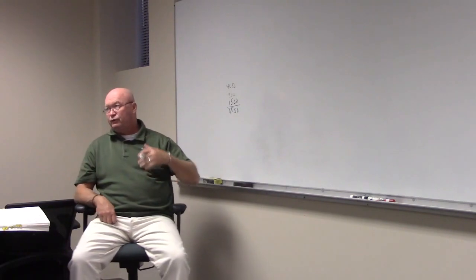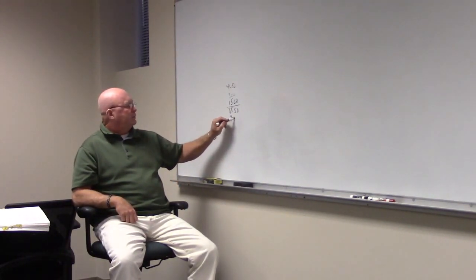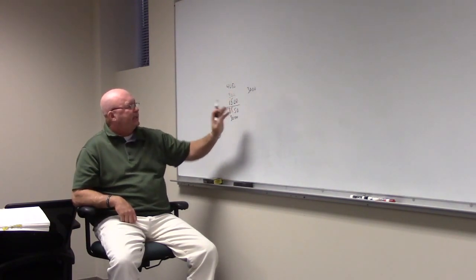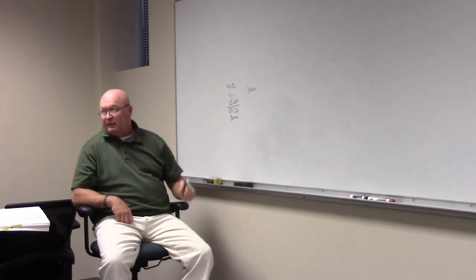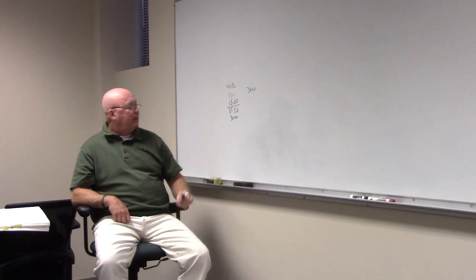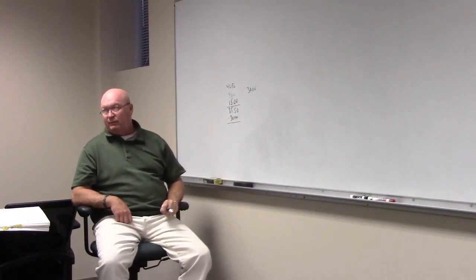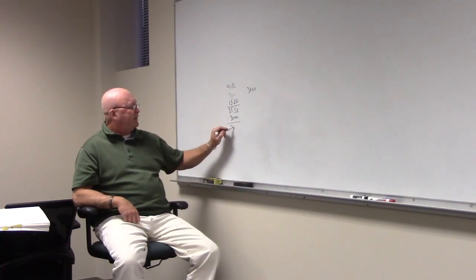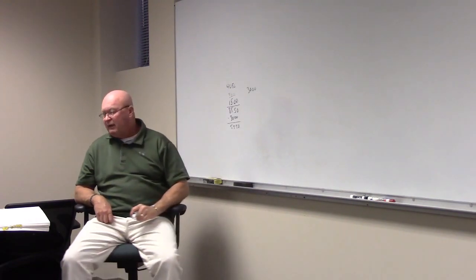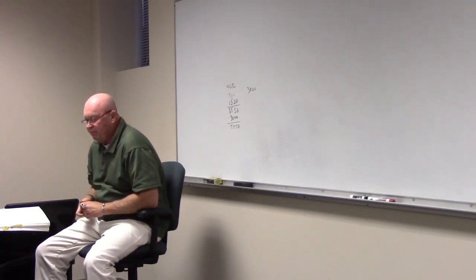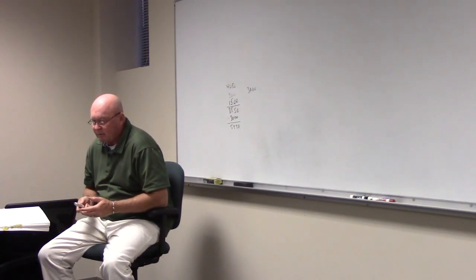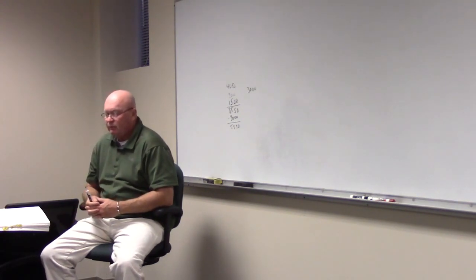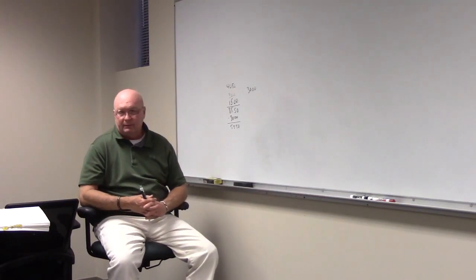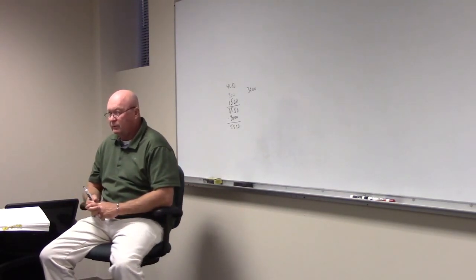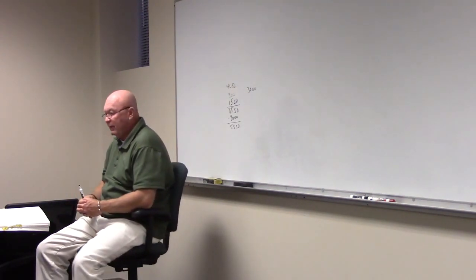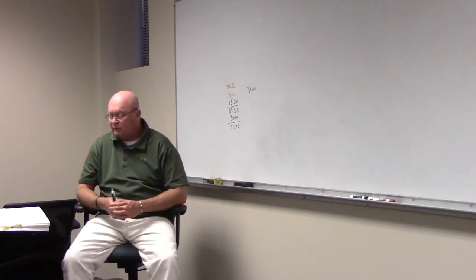All right, it says the first 3,000 is 100%. So I'm going to take that 3,000, I'm fixing to take it out, but I have to count it at 100%. So I'm going to plug it off to the side here. Y'all see what I'm doing? So don't forget it. And now what am I going to do? I'm going to take 3,000 away from that 8,550. And I'm going to get 5,550, is that right? Yeah, 5,550. Now what am I going to do with that 5,550? It says from 3,000 to 120,000, and we definitely don't have that much. What is our demand factor? 220.42 for dwelling. What does it say our demand factor will be for over 3,000? 35%.